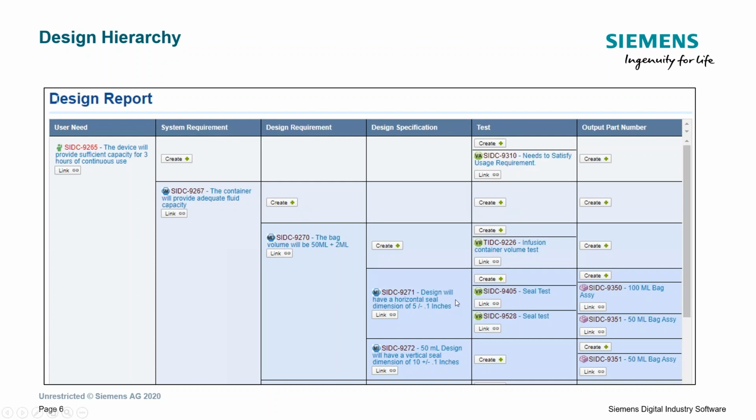So the verification testing is done on some portion of the design, maybe in a bench test or in the different kinds of environments that we do testing for the broken up design. But the validation is done on finished design using end users. And so the difference in these test cases is really what are we testing and who is doing the testing. But when we break out our design, we want to have a very clear delineation between what's being validated and what's being verified because of the nature of the test and the fact that the requirements for the test are different.